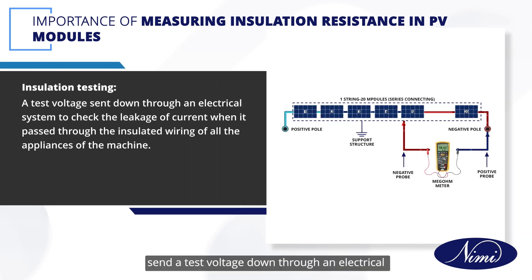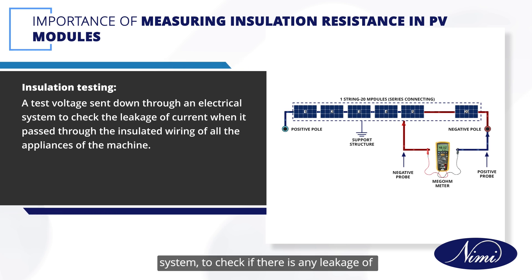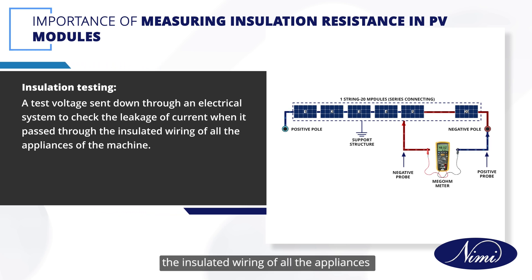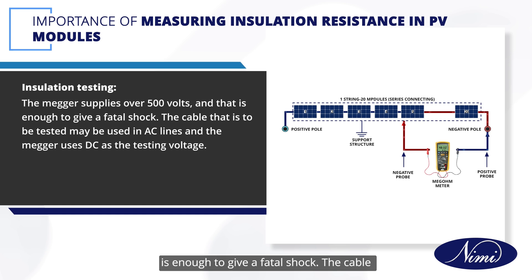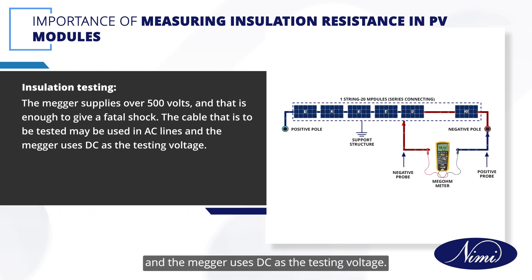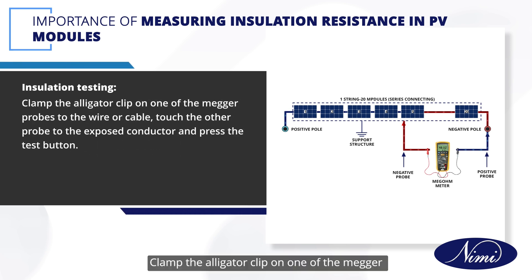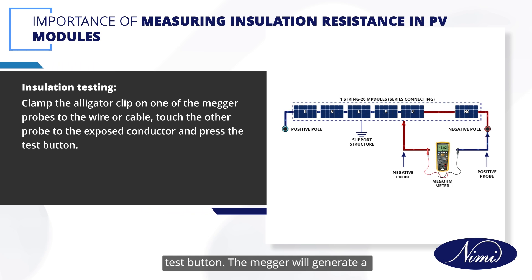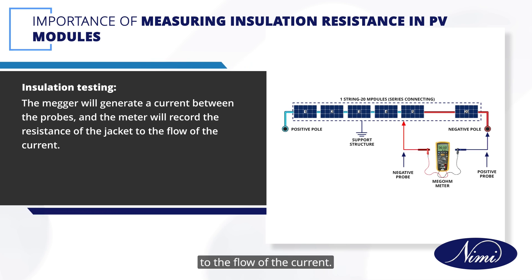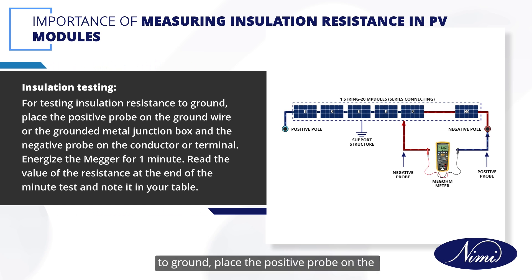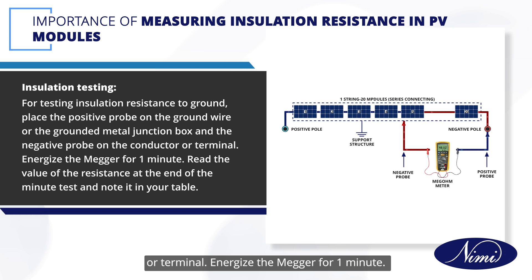In insulation testing using a Megger, we send a test voltage down through an electrical system to check if there is any leakage of current passing through the insulated wiring of all the appliances of the machine. The Megger supplies over 500V, which is enough to give a fatal shock. The cable to be tested may be used in AC lines, but the Megger uses DC as the testing voltage. The Megger will generate a current between the probes, and the meter will record the resistance of the jacket to the flow of current. If testing insulation resistance to ground, place the positive probe on the ground wire or the grounded metal junction box and the negative probe on the conductor or terminal. Energize the Megger for 1 minute, then read and record the resistance value.